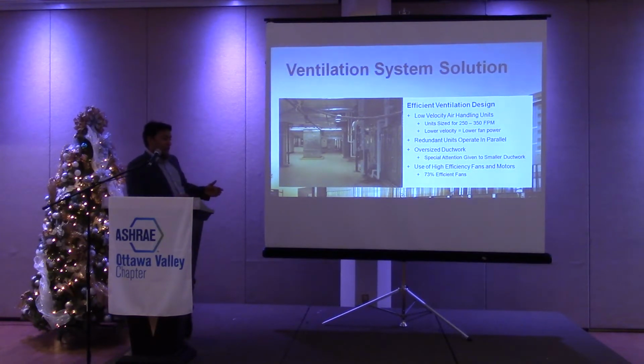All the redundant units where we had those critical spaces, they all operate at 50% capacity all the time. So we get much greater energy savings. We oversized all the ductwork, and we used high efficiency fans and motors. Now, this sounds very simplistic, but the beauty of this approach is that you can't have operators goof this up, right? You have large ducts, you have large air handling units. No control sequence in the world is going to make them smaller, right? Unless they're sticking stuff in the ductwork, the ductwork's going to remain large, and you're going to get significant energy savings.